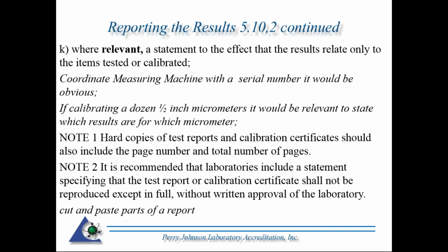Where relevant, a statement to the effect that the results relate only to the items tested or calibrated. Again, I referenced relevant. An example might be where it's not relevant if you're testing or calibrating a coordinate measuring machine with a serial number, basically one item on one report. It may come into play if you're calibrating, say, a dozen half-inch micrometers, all the same make, model. It would be relevant to state which results are for which micrometer.